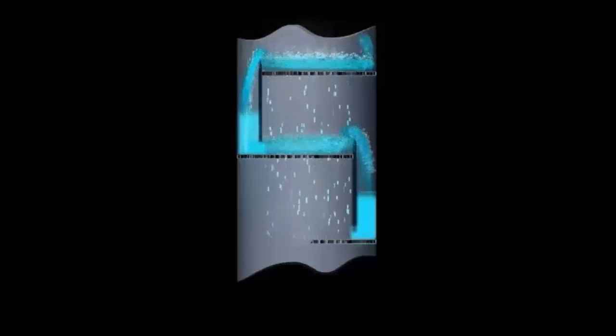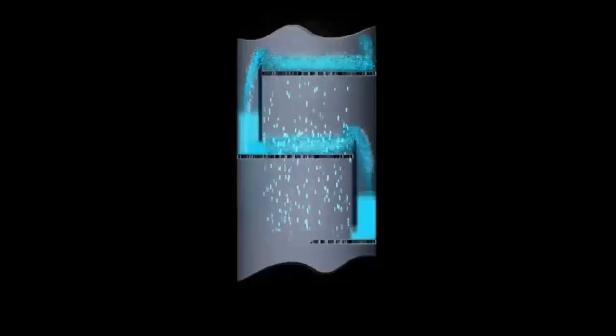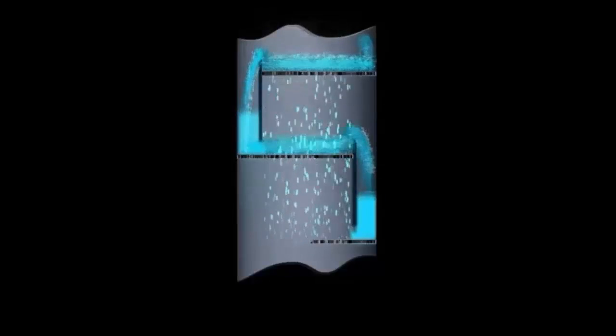An opposite performance problem occurs at low vapor rates: weeping. If the vapor velocity is low, it is possible for liquid to flow down through the tray holes before mixing with the vapor.